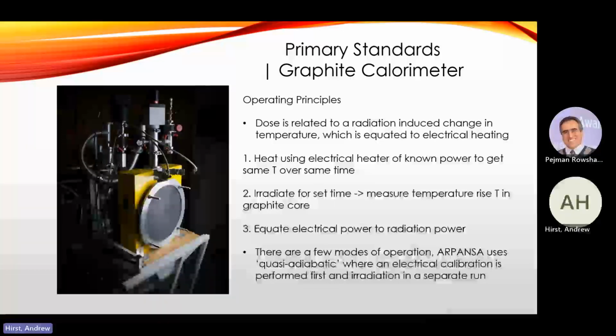As I said, there's a few modes of operation. ARPANSA uses this quasi-adiabatic mode where you do two separate runs, so that's the electrical calibration and then the irradiation. There's other modes where you can do half-half. You heat it up and then you start irradiating, and then you heat it up and you irradiate it, and you try to match that same gradient or temperature increase.